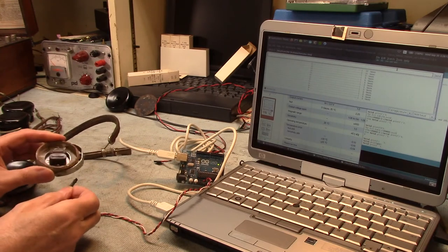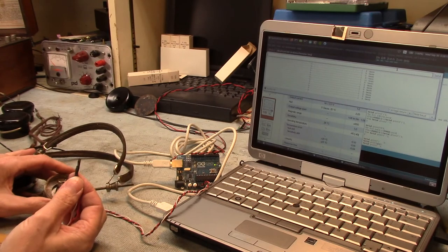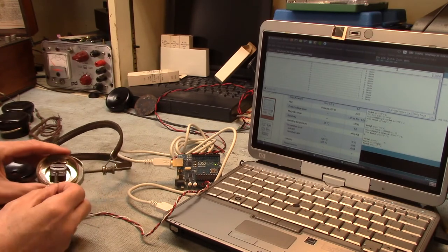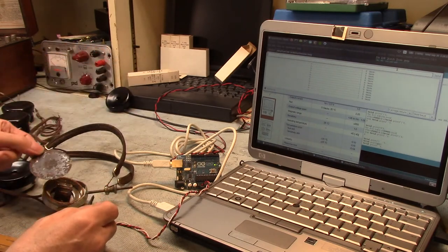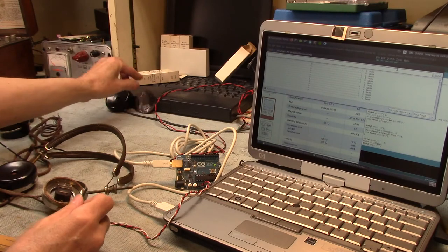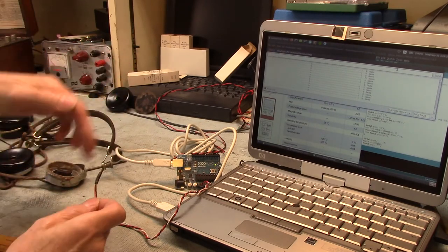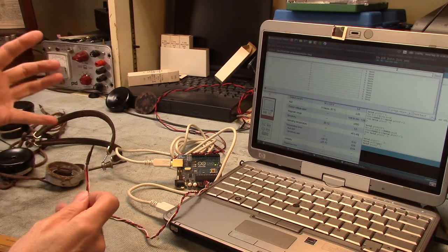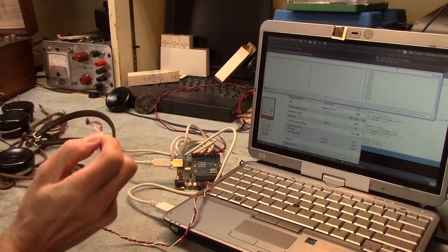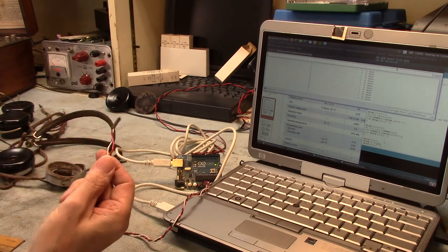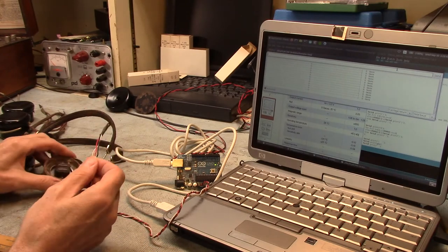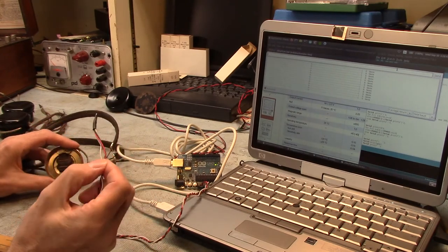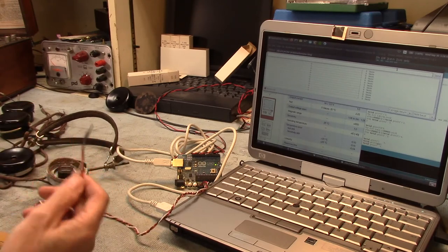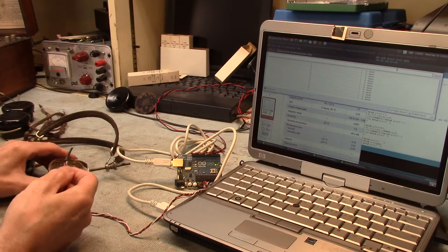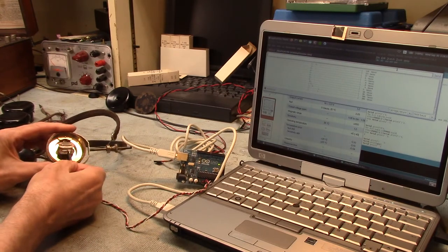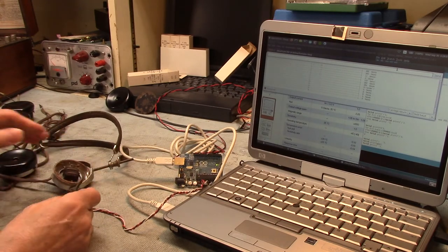But I guess the most useful piece of information is to know where your sensing element truly is, in the plane with, if it's something to do with planes, which in this case is this diaphragm. For a lot of these things, you might have an assembly of magnets and you've got this field inside, and you're dealing with a plasma or something like that. You really care about what the magnetic field is inside where the plasma is. And that's what you might use a Hall effect sensor for: you test your assembly out before you put it in your device. You're looking for that field strength out in space, as it were, of this whole assembly. And that's what a lot of magnetometers and Gauss meters are used for. For something that you're measuring on the surface, you've got to account for where on the surface plane-wise that sensor is.